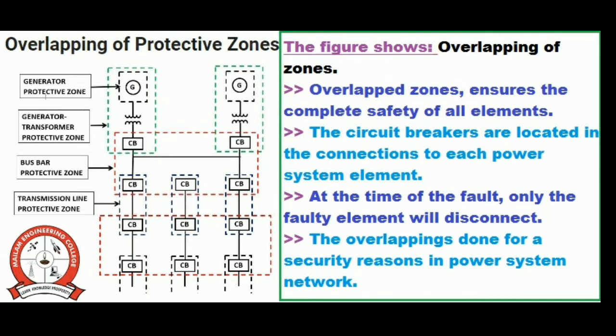The various components of the protective zones include generators, transformers, busbars, transmission lines, cables, and so on. There is no part that has no protection in the power system. In practice, these zones overlap to ensure the complete safety of all elements of the system. The part of the system which is unprotected is known as a dead spot or blind spot. To avoid dead spots, we use overlapping of zones, as shown in the diagram.